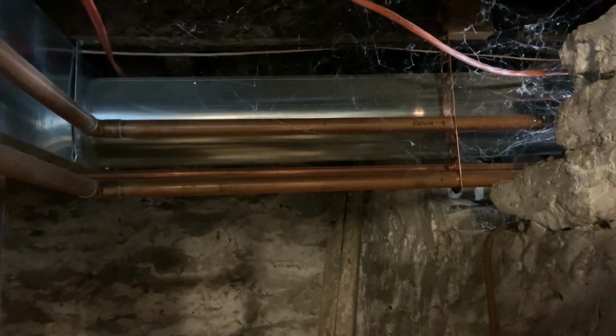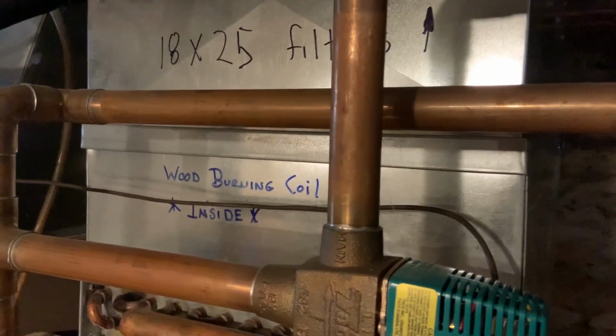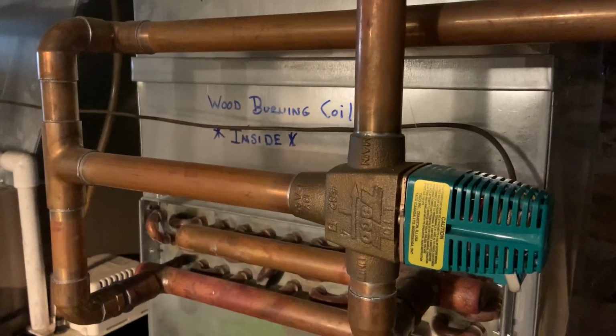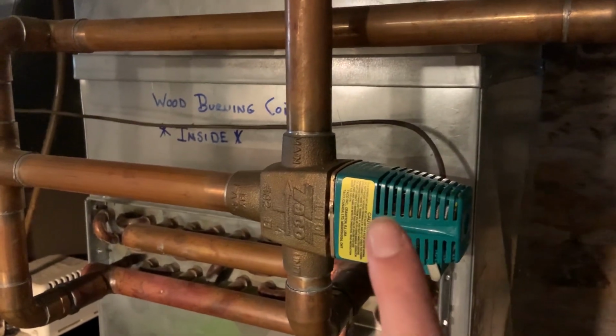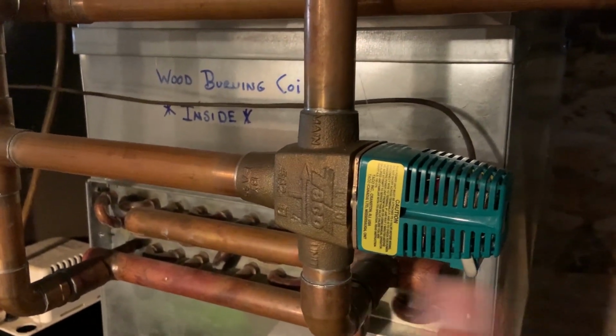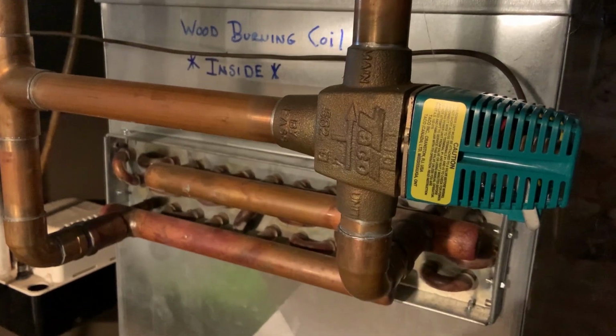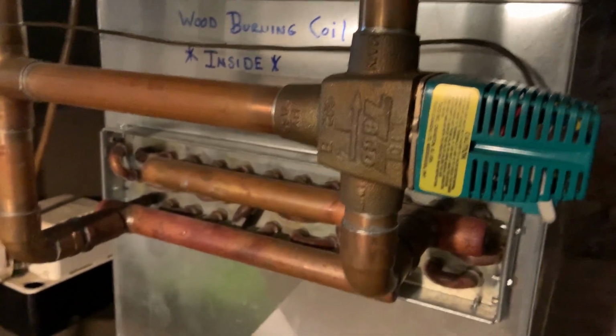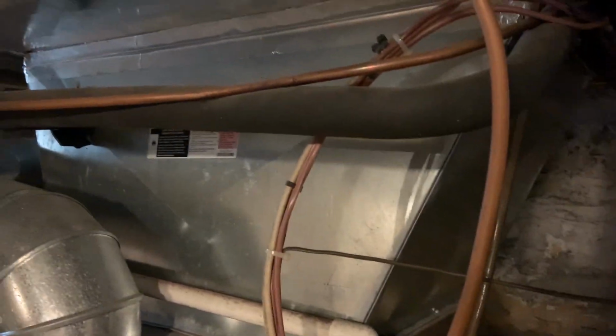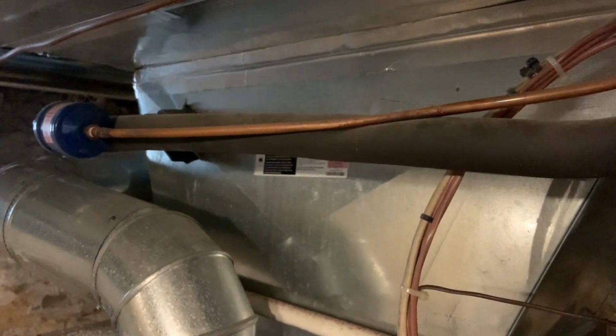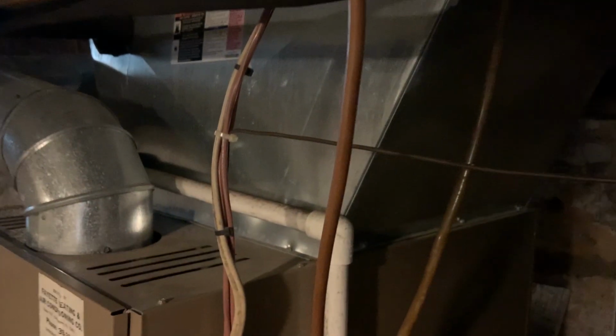The supply line here is on the very bottom. It comes across into the return duct of my forced air furnace. This actually works as when the house calls for heat, it opens up the valve that's inside of this and allows hot water to run into the coils. Because the ceiling is so low in my basement and I have central air, which is right here, this heat exchanger here could not be stacked on top of the plenum. So we had to put it in the return.